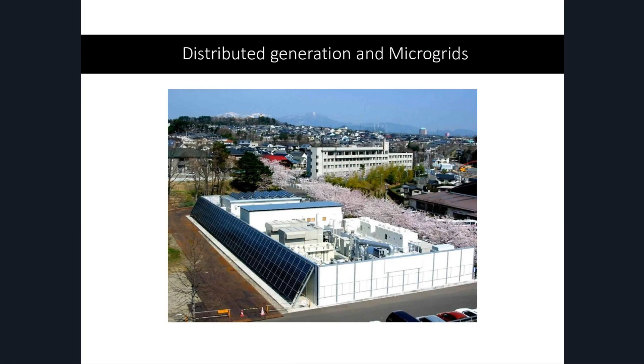This fire station in Fremont got noticed. They created their own fire grid, their own microgrid, because they have backup diesel gensets as backup power, but their diesel supply only lasts 72 hours. Now we're seeing week-long outages, and gas stations are closed so they can't run. You may not get diesel, so your fire station, grocery store, or hospital may be out of luck after 2 or 3 days.